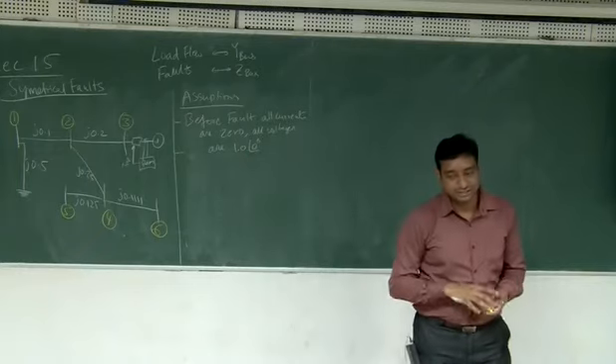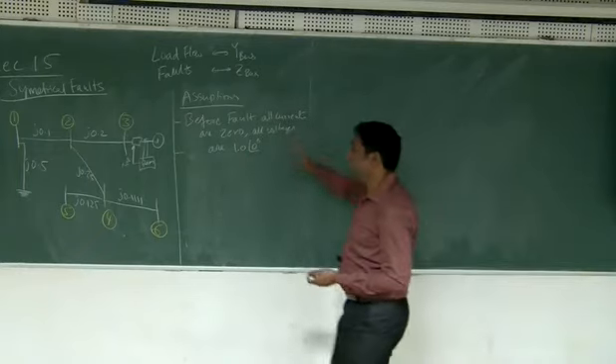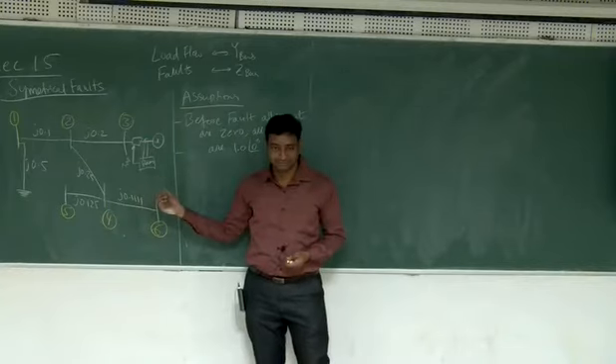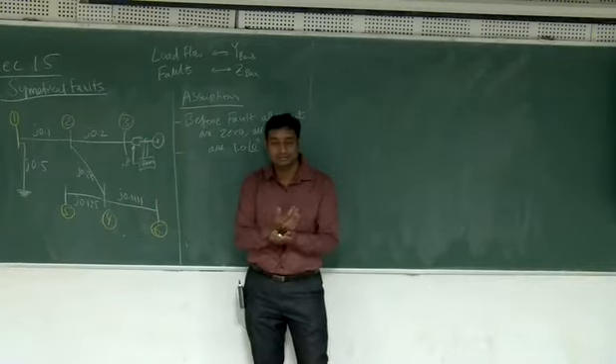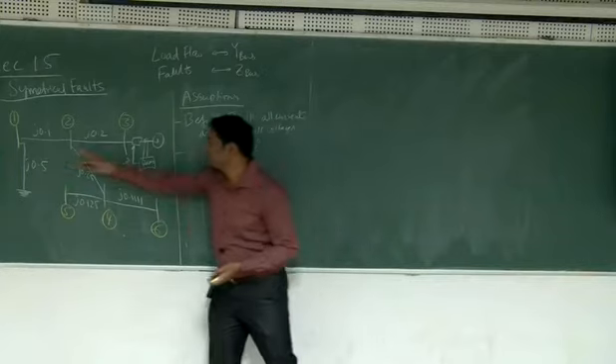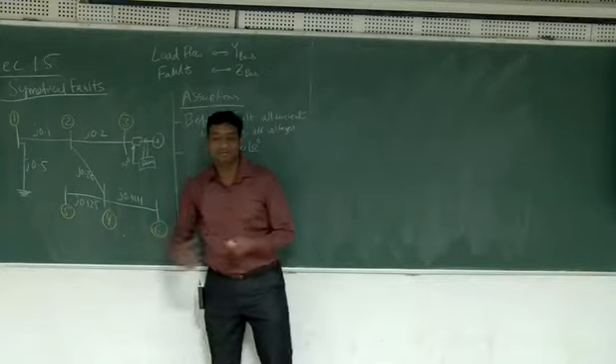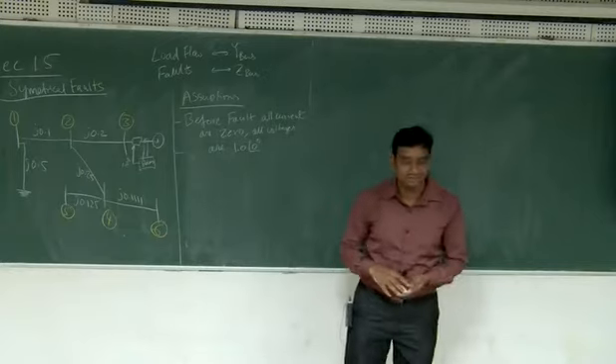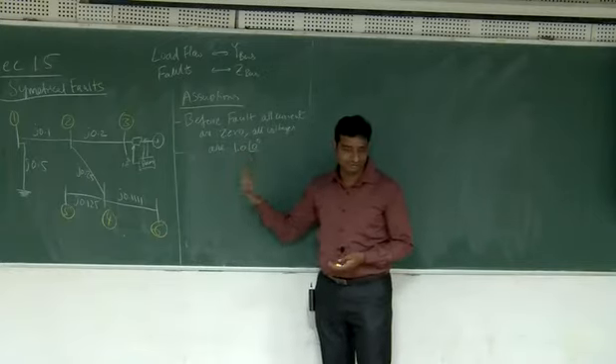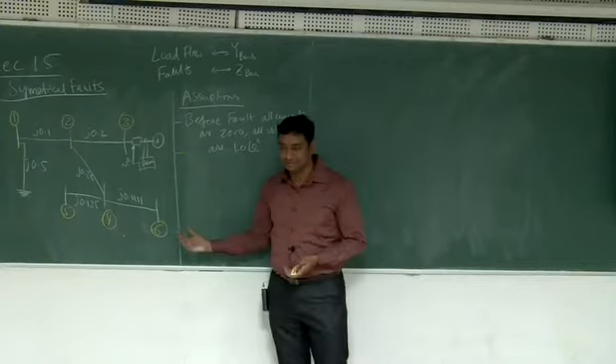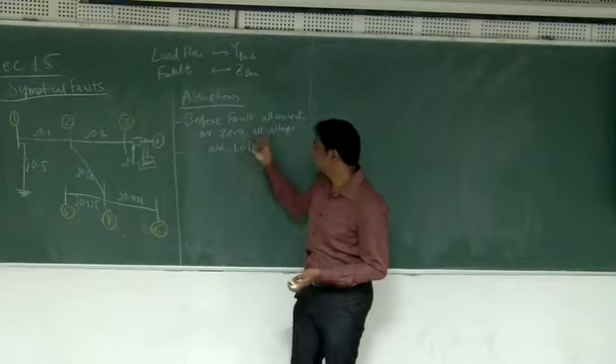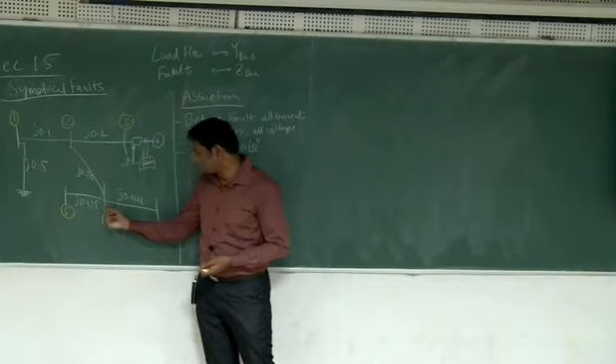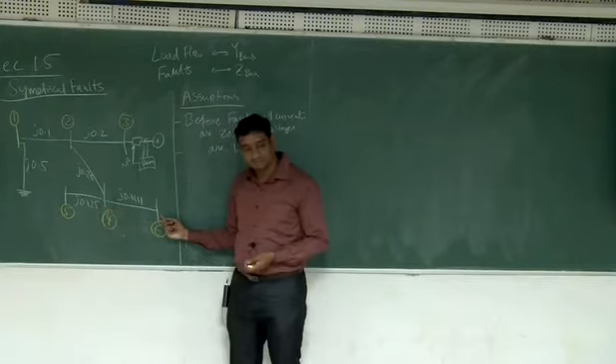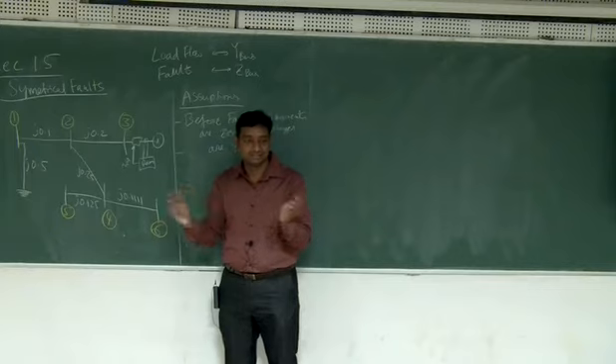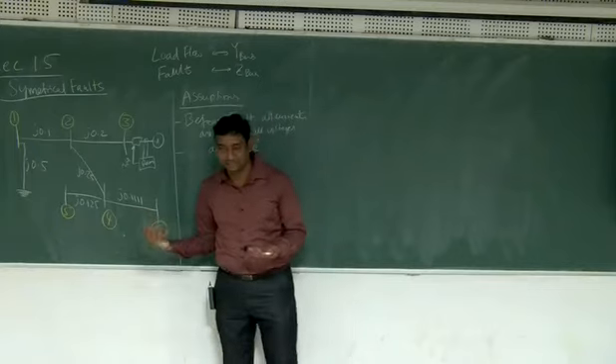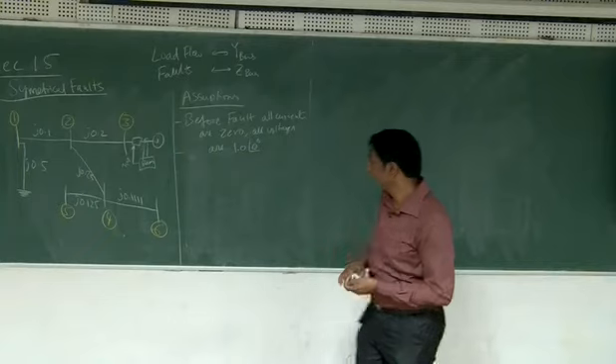So normally what is the procedure? This is not the procedure. What you will do is you will solve the load flow problem. The results of the load flow problem is you will know what are the unknown states. You will know all the voltage, actual voltages of all these buses. But we don't want to do that. So it's a simplifying assumption that all the voltages are 1 angle 0. And all the currents are also 0. So in fact these two are obvious, because suppose if the voltage here is 1 angle 0, the voltage here is also 1 angle 0. Angles are same. There is no angle difference, so there won't be any current, and all the currents are also 0. So it's just a simplifying assumption.